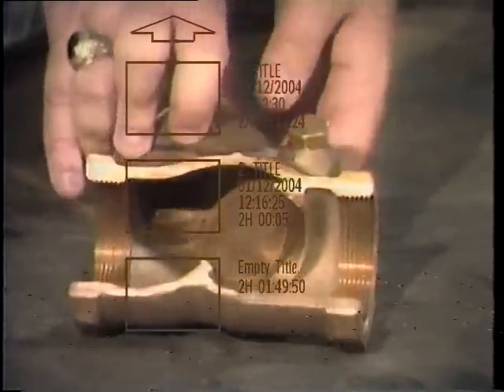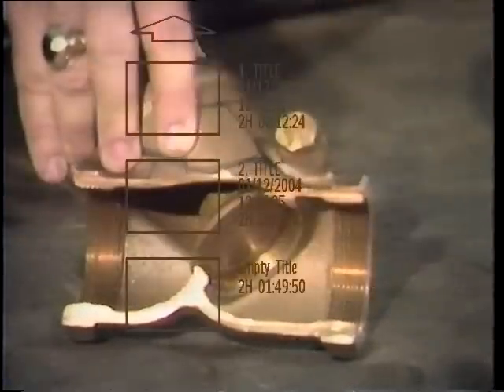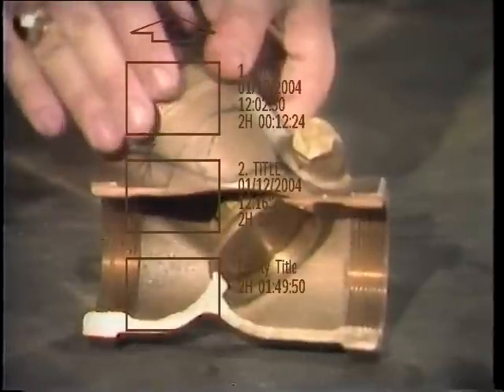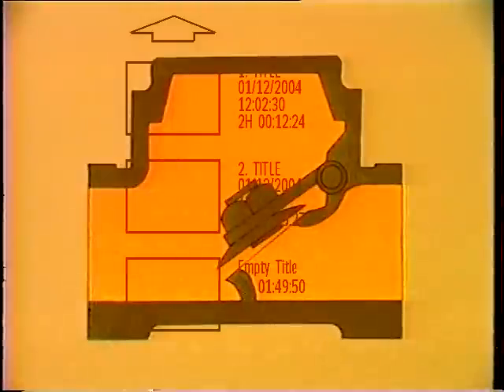There's one more basic valve design to talk about before we break: the check valve. A check valve will permit flow in one direction only — it is designed to prevent any backflow of fluid within the piping. However, most check valves cannot be used as stop valves; most will only close if the flow stops or if for some reason tries to reverse its direction. There are three basic types of check valves: the swing, the lift, and the stop check.